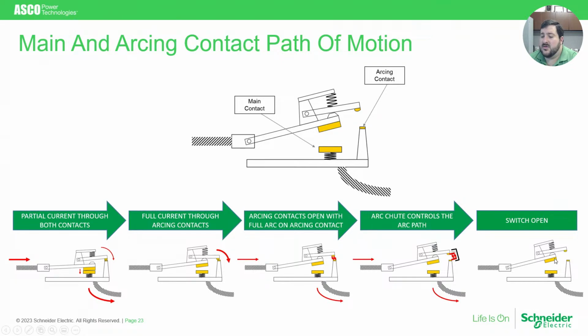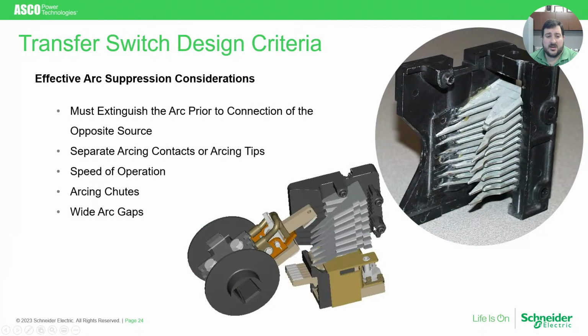And like I mentioned, the arcing contacts are designed to be easily inspectable and replaceable if necessary, although they usually do last the life of the equipment, even when they're doing their job of protecting the main contacts. The arcing chute that I mentioned is this metal blade sheet looking component here. It's difficult to describe, but you can see how the arcing contact opens and closes by swinging through the grooves and channels cut into these metal sheets.